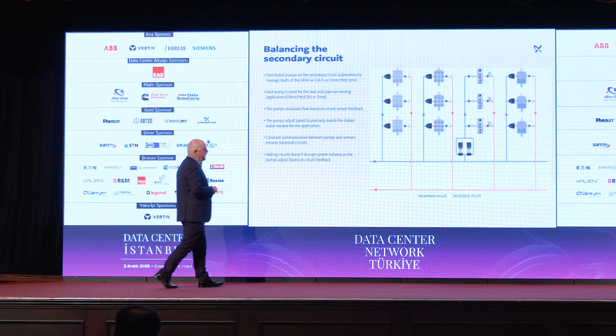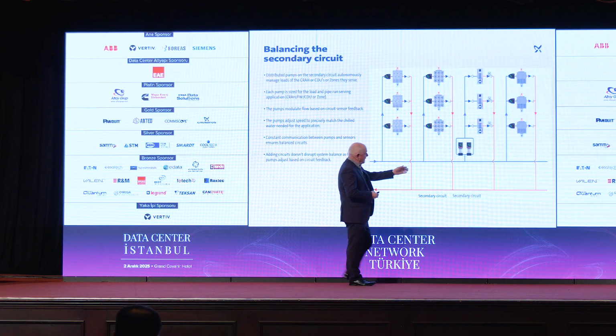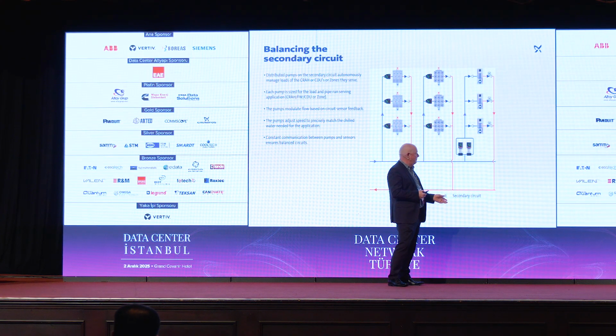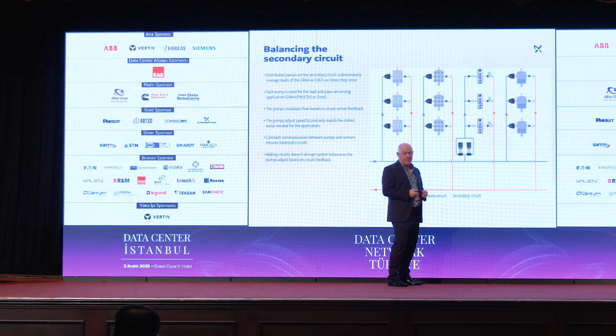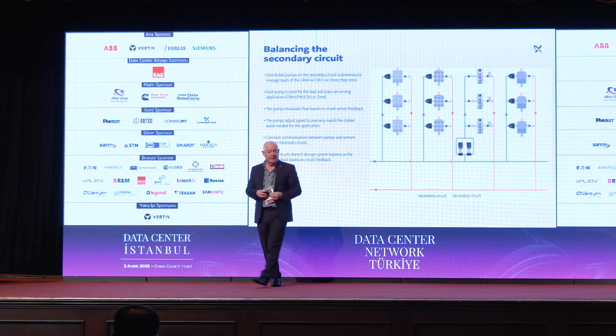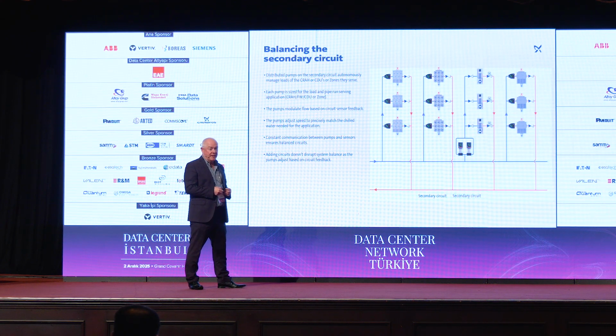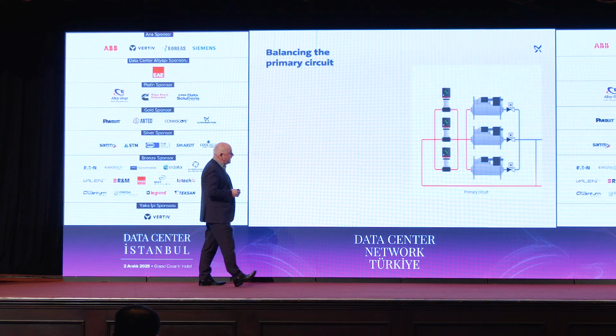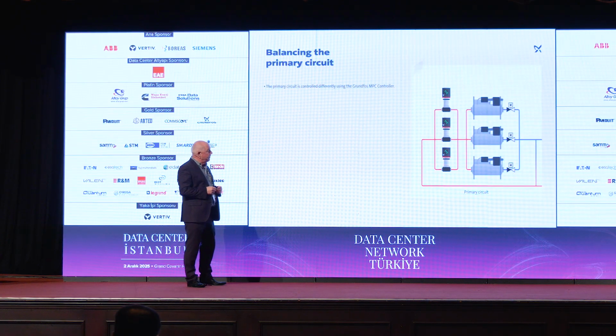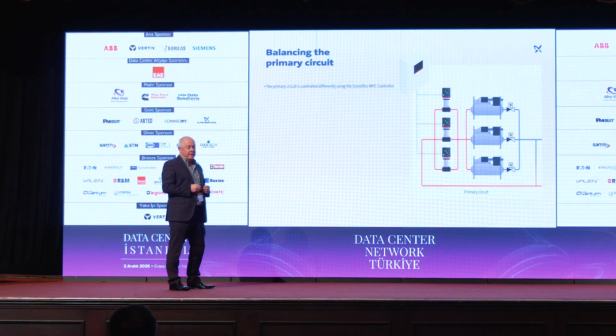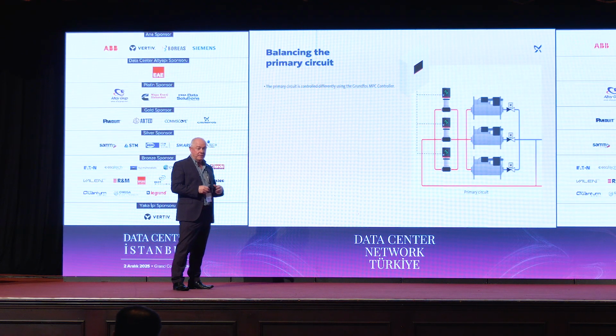And if we want to put extra onto the system, as you can see, we put on a new load and we put pumps on that load as well. The primary pumps obviously have to be sized to meet that full load, but we can look at that through the design phase or add on in a modular way. We can add on to the primary load as well. And how we balance the primary and secondary side then, if we look at the primary, the first thing that we do is we use a controller. We call it an MPC controller. It's a standard controller that we use in all our HVAC applications, so there's nothing strange about this. The pumps themselves are standard pumps. They're just worked in a slightly different way.